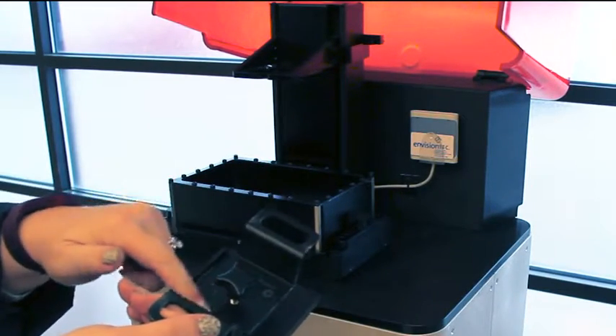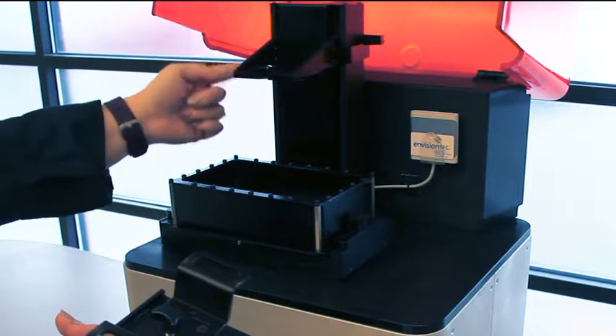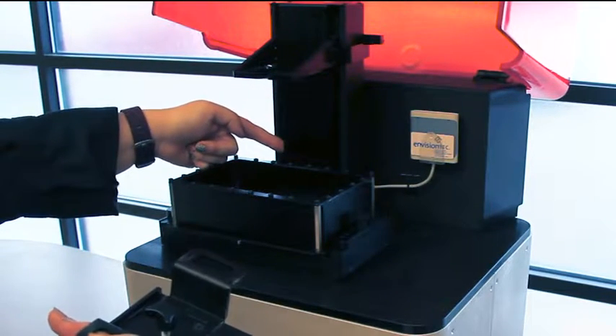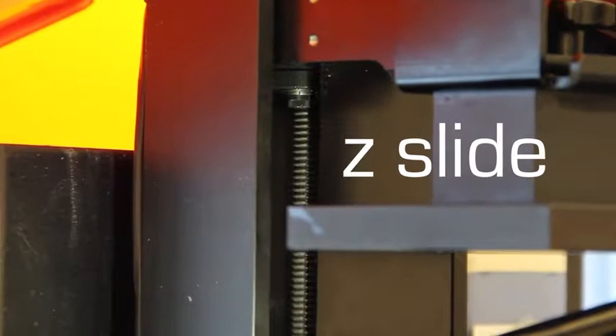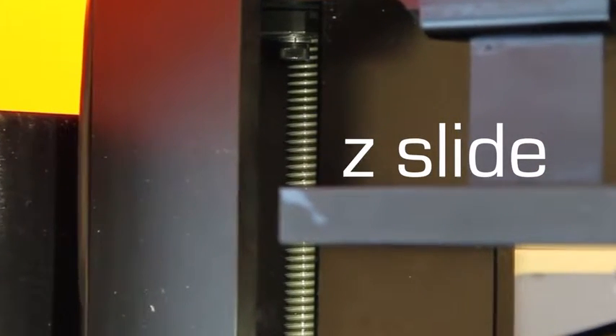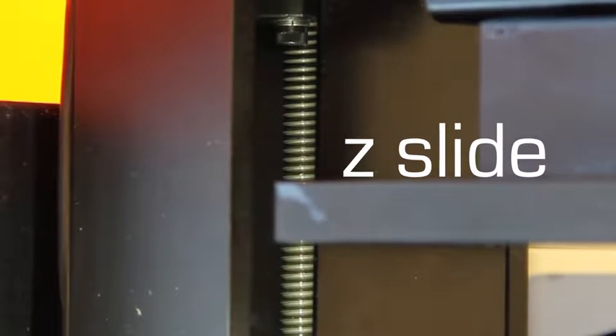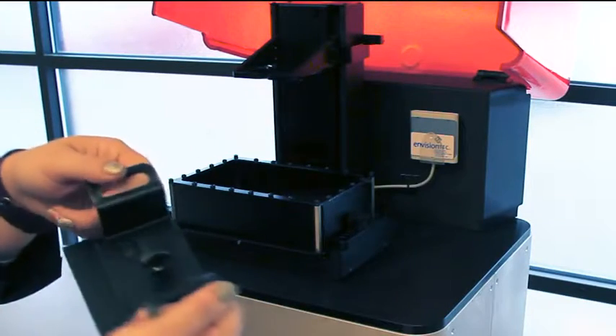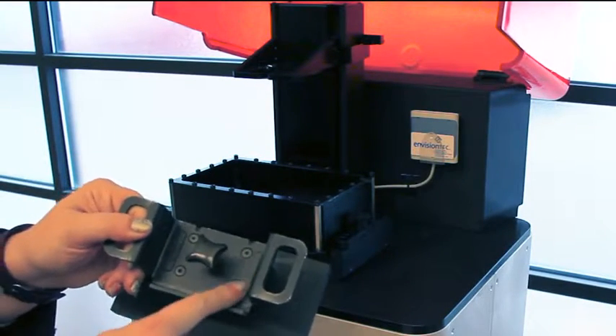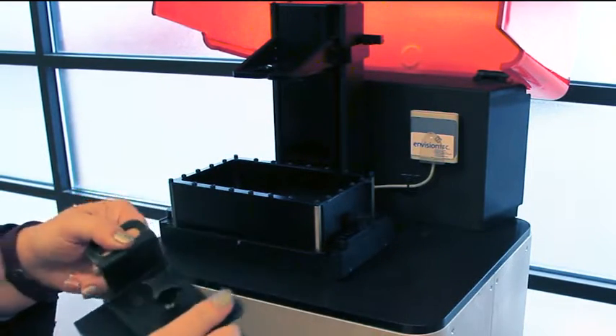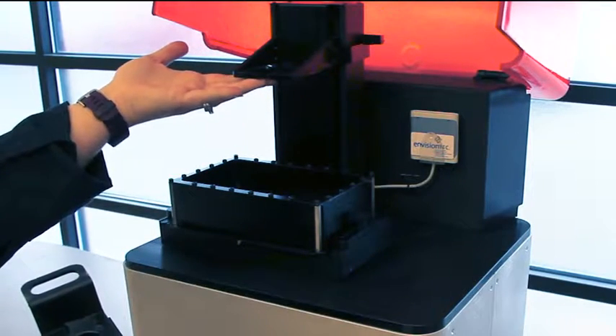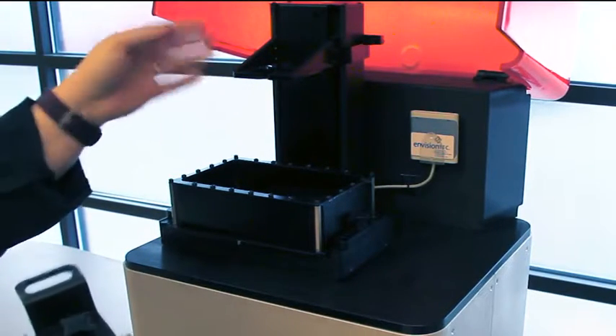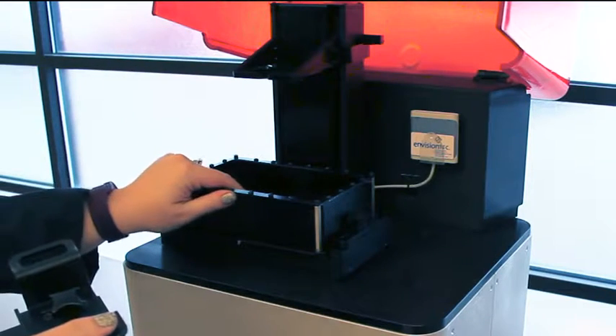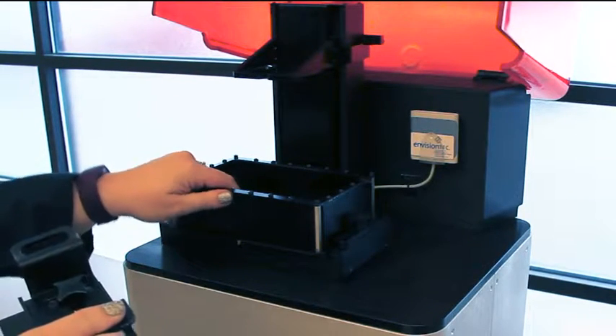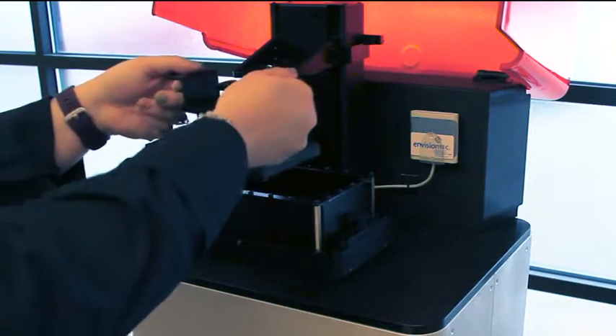This is the mating surface that meets the arm that is on the Z slide. The Z slide back here is the heart and soul of the machine. We will want to oil that probably about once every 6 months. Before putting this back on, you always want to make sure the surface right here is clean and this surface right here is clean. If they are not clean, this platform becomes not parallel to the basement, which we're going to talk about next. So I'm going to slide this in.